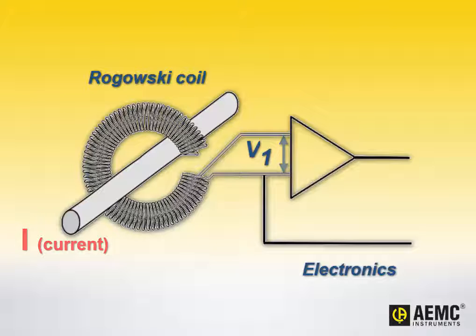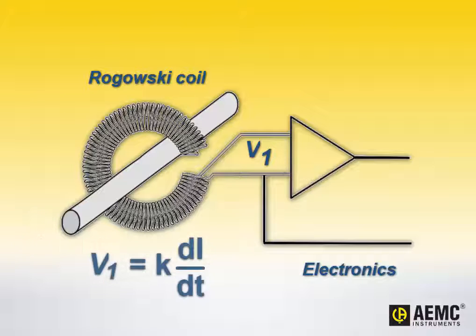Calculating current from V1 requires the formula shown on the screen. In this formula, K is a value derived from the physical characteristics of the coil. These include loop size, the number of turns, and the length of the winding. Di over dt represents the change in current over time, which is dependent on the current's frequency.